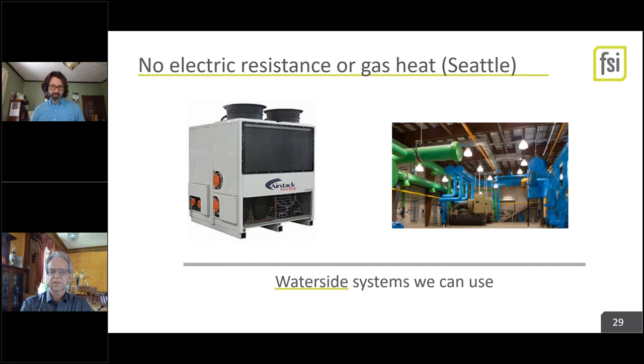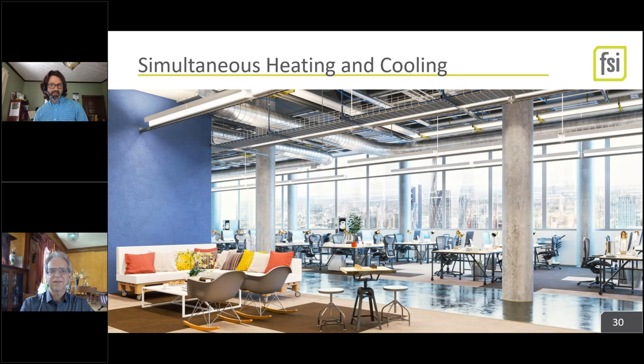You know, that's not a thing you're gonna build until you're a campus or a very large building or a campus scale, really. Next slide. Simultaneous. Yeah, and I'm still not getting an update, but if you can hear me, I'm just gonna go with it. Simultaneous heating and cooling. Special note, you get 10% of your floor area in open area before you need to do some things where one thermostat needs to talk to another thermostat. And so it's not really a big deal, but it really does matter that you're not putting cooling in over here and heating over here and just blowing air across the two. That's a really healthy energy sink.